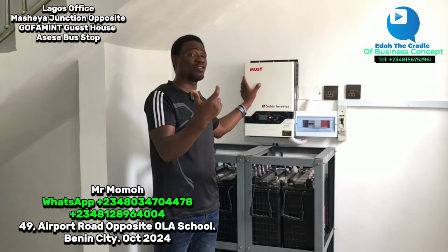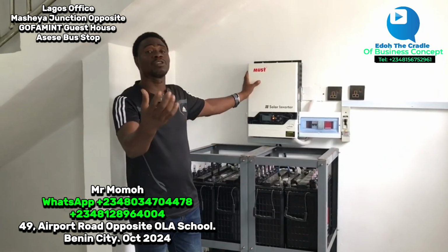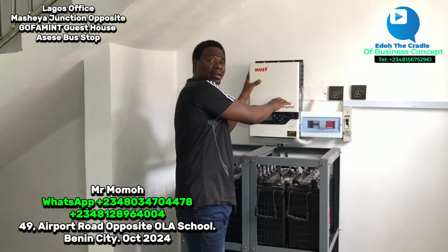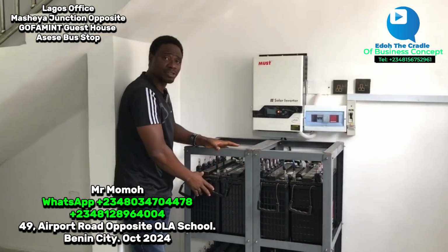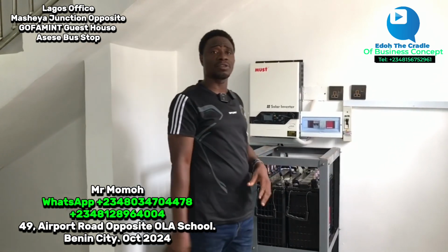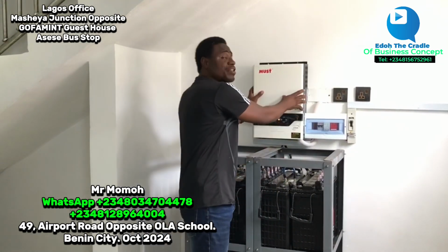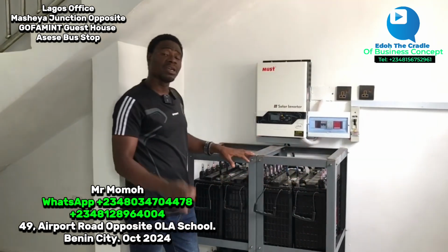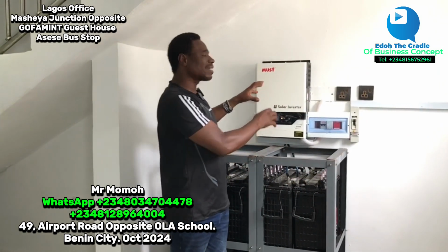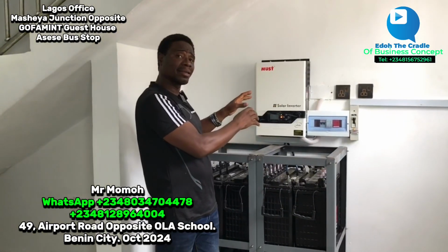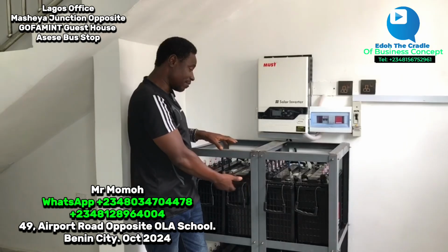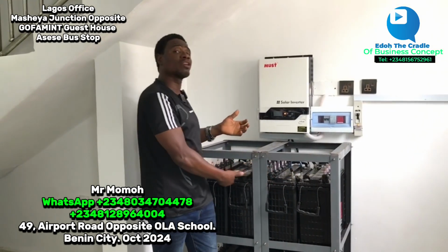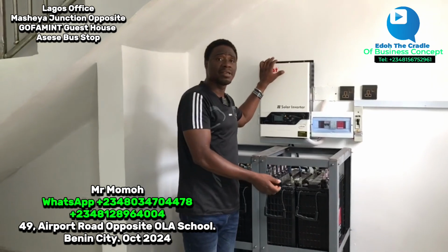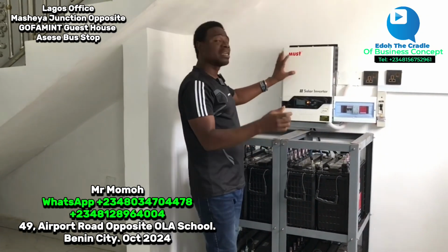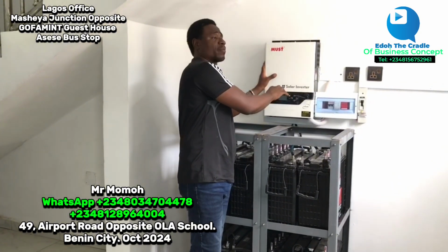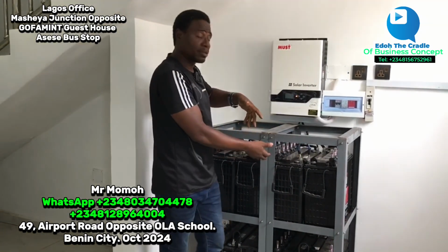When I talk about lithium, or even not lithium, you see situations where people carry a 10 kVA inverter and put it with only 4 batteries. The truth is that this is wrong installation. To put a 10 kVA inverter with 4 batteries is wrong, because that 10 kVA is high. If you look at the power of the batteries, that's almost 10 kilowatts. So if you put a 10 kVA inverter, the question to ask those installers is: is it possible to put a 10 kVA inverter on just 4 batteries?